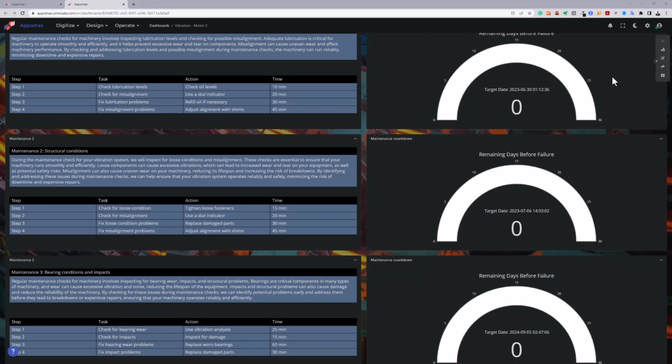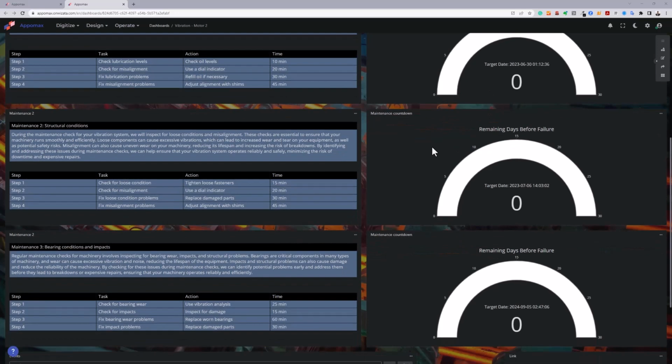The way we determine the unacceptable level is from the initial teaching of the model. We can run the training right after maintenance, or we can choose the baseline based on the best condition motor, and we can then forecast up to an unacceptable level.